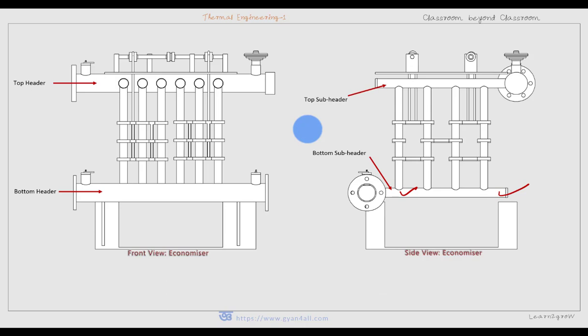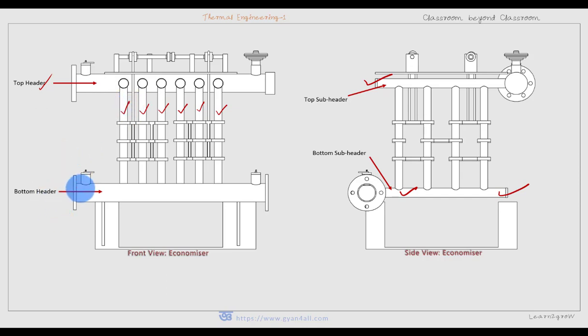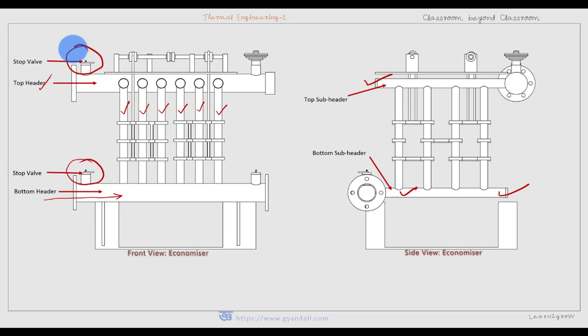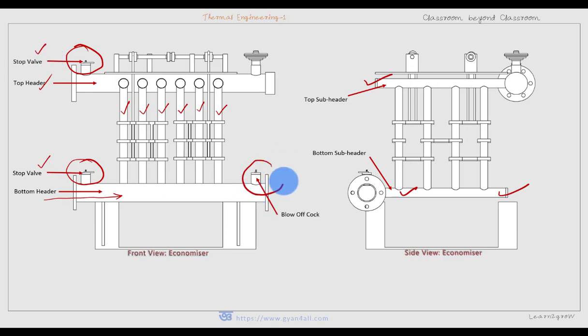The top sub-headers are the horizontal tubes at the top, and all these horizontal tubes are connected to the top header. Water from the bottom header moves up to the top header through the vertical tubes. As the water enters the bottom header, there is a stop valve. At the top, there is another stop valve for the hot water outlet. The bottom one is for cold water inlet. There is also a blow-off cock at the bottom header to discharge sediments that may be deposited there.